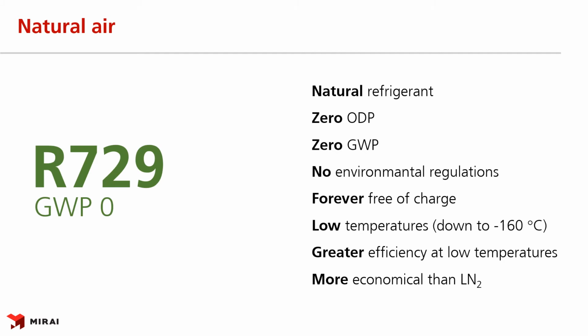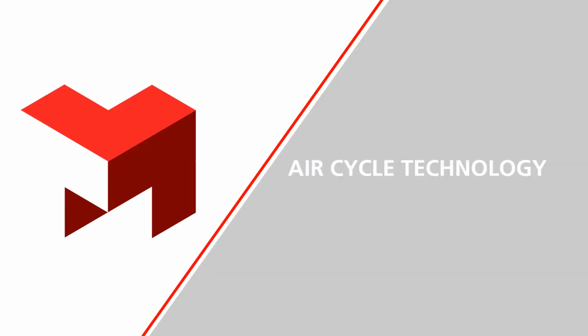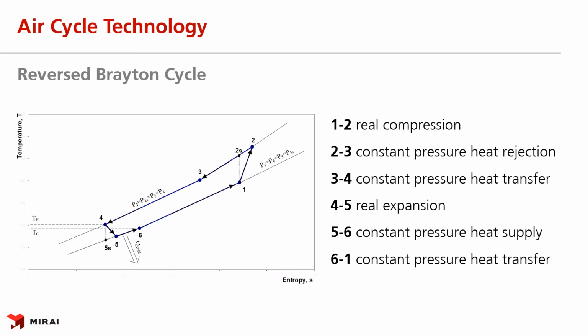In special cases, air can reach up to -160 degrees Celsius. Air has greater efficiency in the ULT range than other solutions used. And last but not least, air is more economical than liquid nitrogen when running costs are considered. With air as refrigerant, we need to cover some basics of the Air Cycle Technology first. How does it work from the perspective of thermodynamics?